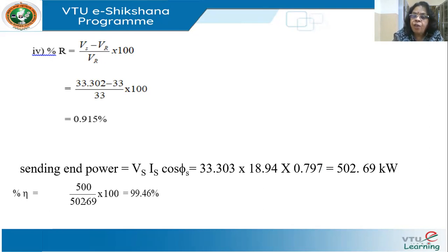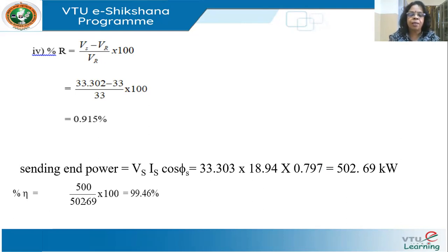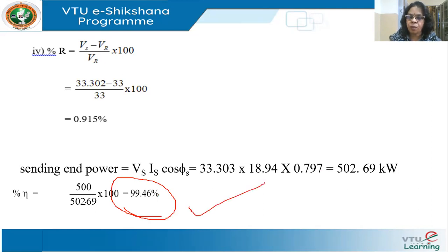For the efficiency, the sending end power for single phase is VS·IS·cos φS = 33,303 × 18.94 × 0.797 = 502.69 kilowatts. Therefore, efficiency = output / input × 100 = 500 / 502.69 × 100 = 99.46%. Very good efficiency.